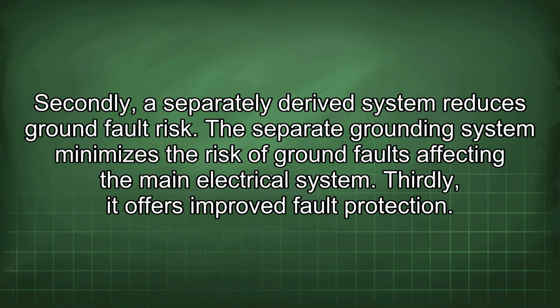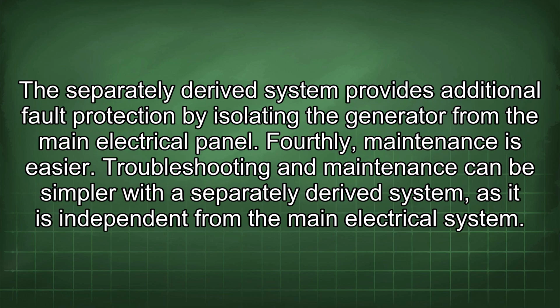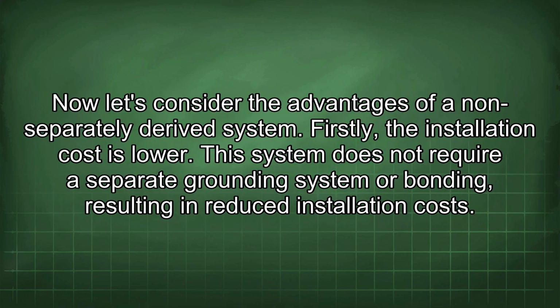Thirdly, it offers improved fault protection. The separately derived system provides additional fault protection by isolating the generator from the main electrical panel. Fourthly, maintenance is easier. Troubleshooting and maintenance can be simpler with a separately derived system, as it is independent from the main electrical system. Now let's consider the advantages of a non-separately derived system.